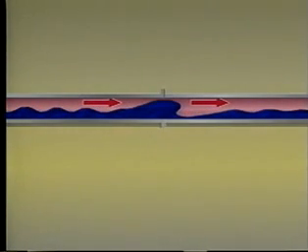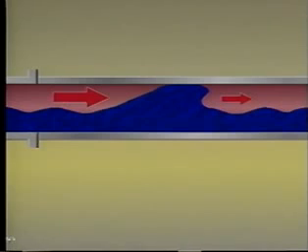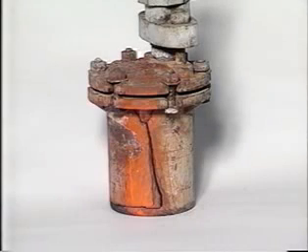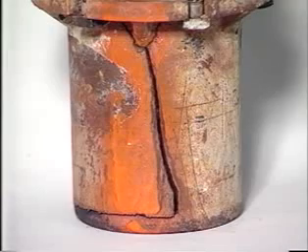If this gas flow causes condensate waves to rise and fill the pipe, a seal is formed with the pressure of the steam behind it. Since the steam cannot flow through the condensate seal, pressure drops on the downstream side. The condensate seal now becomes a piston that is accelerated downstream by virtue of this pressure differential. As it is driven downstream, the piston picks up more liquid that is added to the existing mass of the slug and velocity increases. This is differential shock. If the slug gains high enough momentum and is then required to change direction at a tee or elbow or is stopped by a valve, great damage can be done.